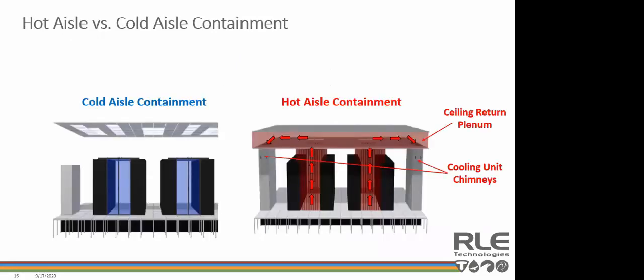Thanks, Tim. So there's two main types of containment typically installed in data centers. There's cold aisle containment and hot aisle containment. As the name implies, cold aisle containment contains cold aisles, hot aisle containment contains the hot aisles. Beyond that, there's a couple more distinctions. Cold aisle is containing the cold air supply, which means the rest of the data center is at the hot air or the hot return air temperature. Typically, cold aisle containment contains the cool air from the floor to the top of the server racks, or in some cases with soft curtain containment all the way to the ceiling and at the ends of the aisles.